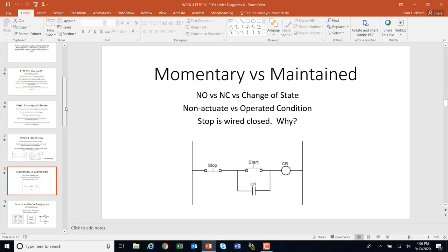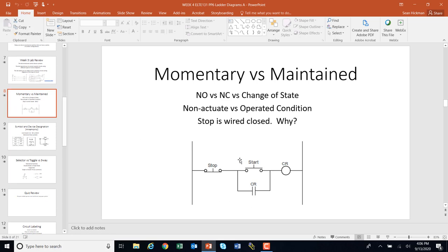We are talking about our memory circuit right here. We have a normally closed stop button — that's what's depicted — and then a normally open start button. These change state when we actuate them. Because this is normally closed, if I actuate the stop, it opens. This is normally open, so if I actuate the start, it closes. The stop has a normally closed contact. When it's activated, the normally closed contacts don't become normally open contacts — they just become actuated so they're no longer closed; they become open.